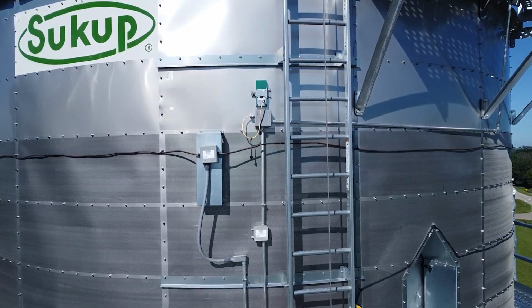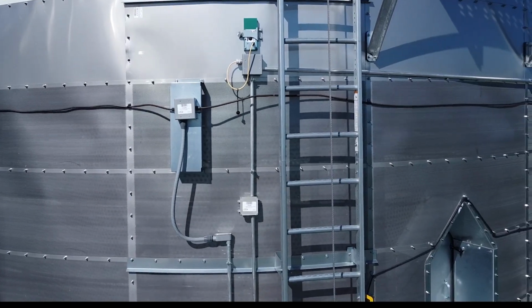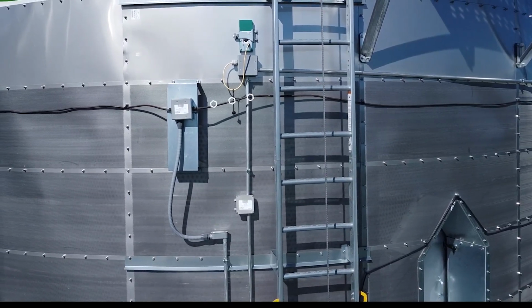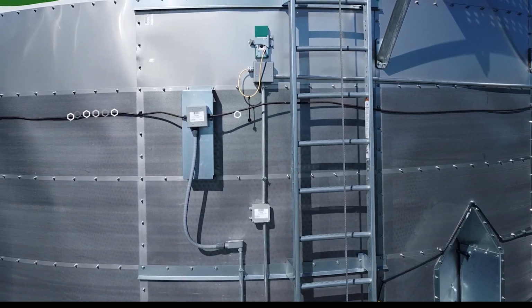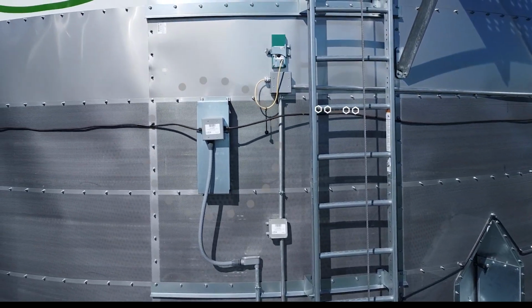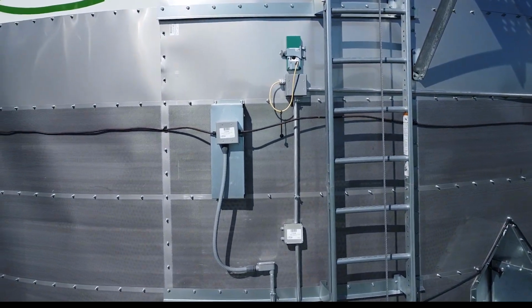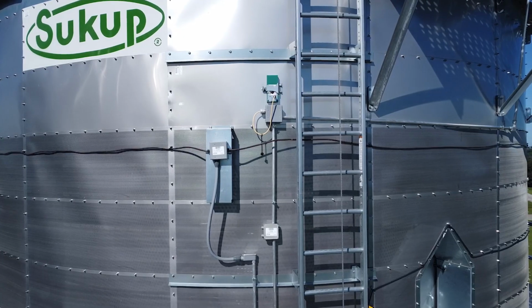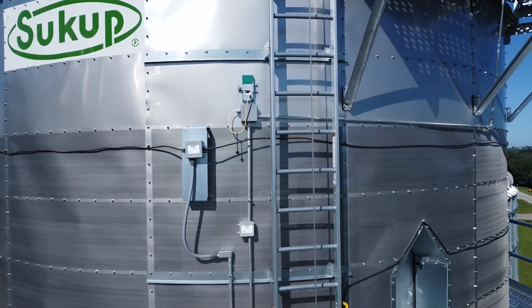And then just down from that, we have the upper column over temp. It's a copper tube that stretches all the way around the dryer. There's a left and a right. They basically have a junction box in the middle. If you get an upper column over temp, you can't necessarily take for granted what's left or what's right. You have to take a voltmeter up there and figure out which circuit is open.